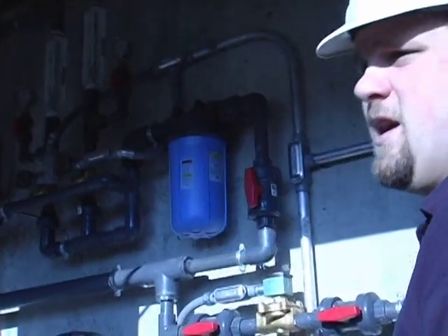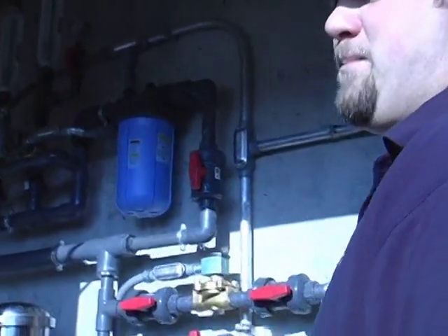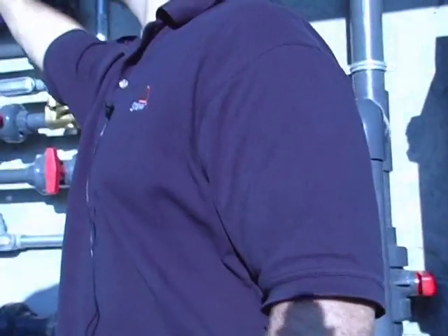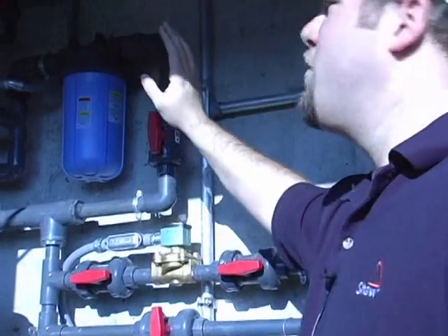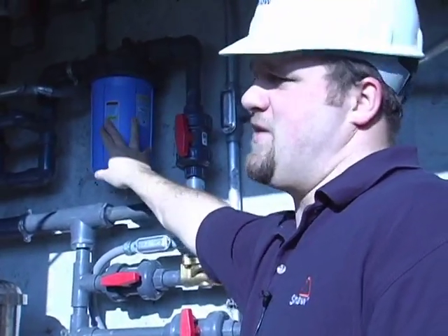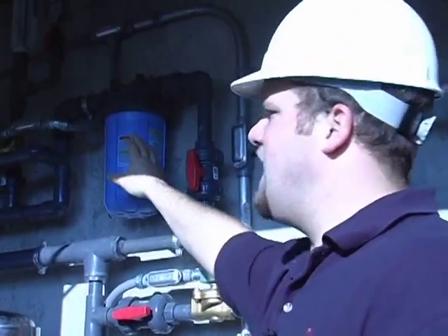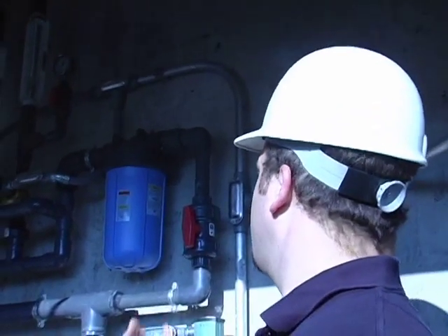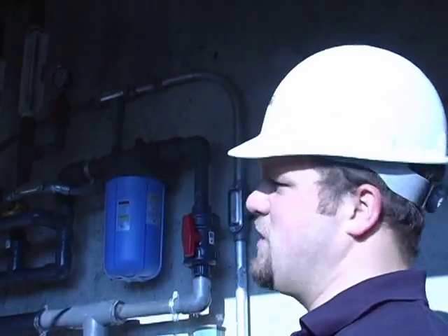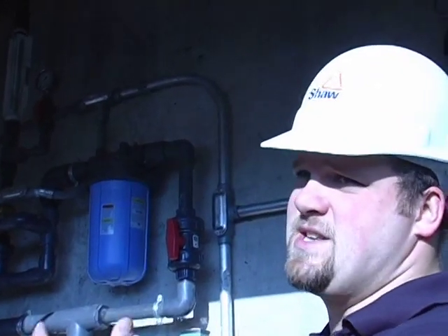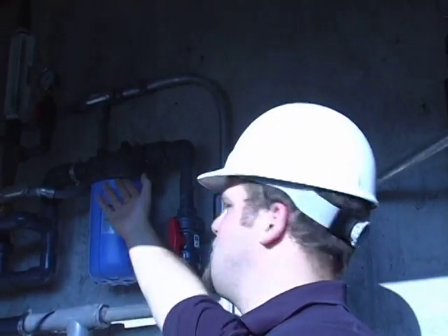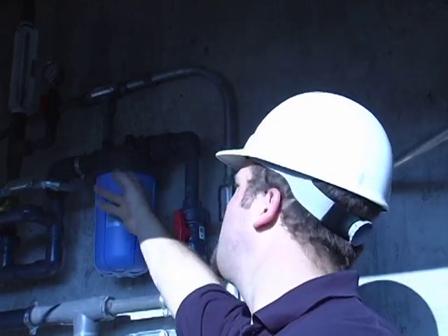In order to do that, there's just this little plastic filter wrench here. You can just put it over the body, and it screws off. If you ever do maintenance on this filter or cleaning, when you take it off, there's a little rubber ring seal on there. You want to make sure when you screw that back up that it seats evenly in there. Otherwise, you will see some leaking come out of this.